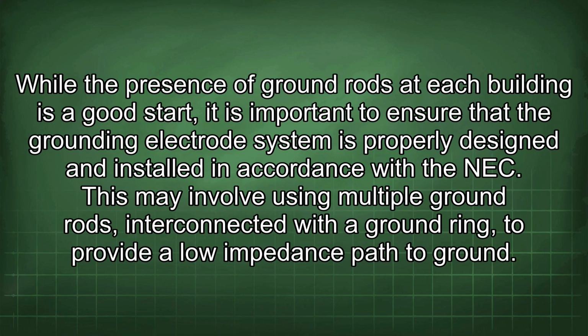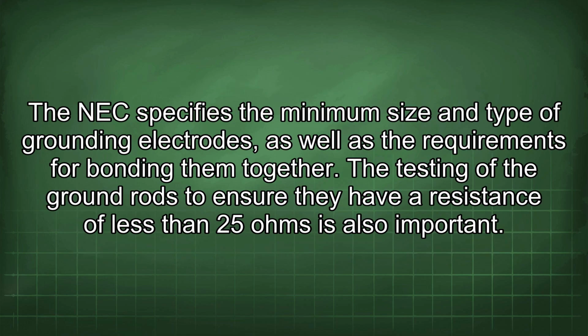While the presence of ground rods at each building is a good start, it is important to ensure that the grounding electrode system is properly designed and installed in accordance with the NEC. This may involve using multiple ground rods interconnected with a ground ring to provide a low impedance path to ground. The NEC specifies the minimum size and type of grounding electrodes as well as the requirements for bonding them together. The testing of the ground rods to ensure they have a resistance of less than 25 ohms is also important.